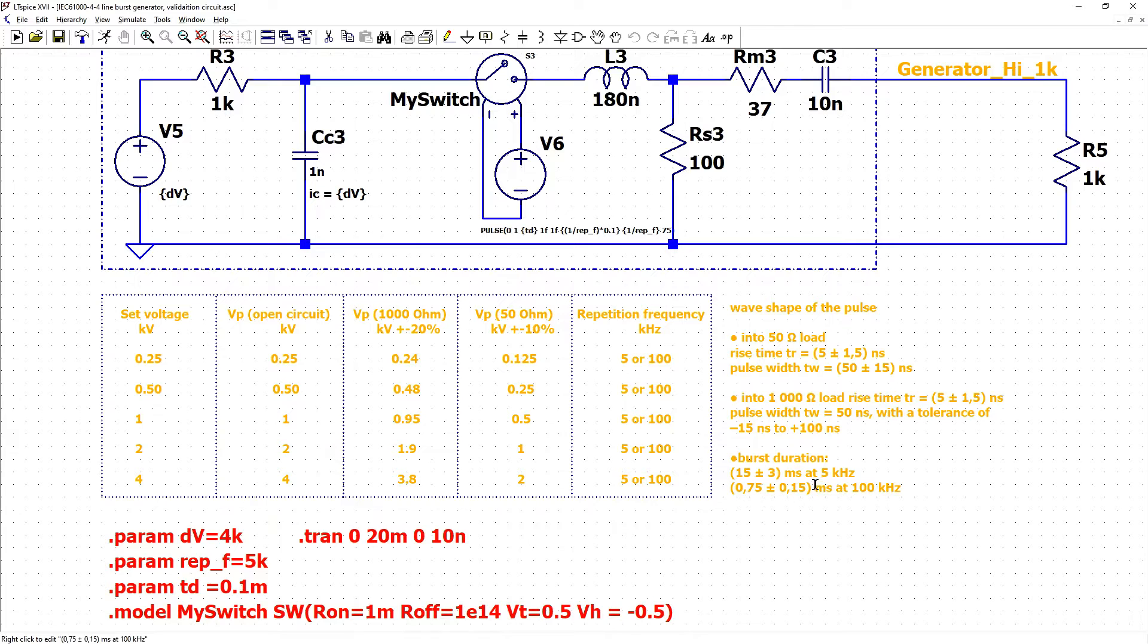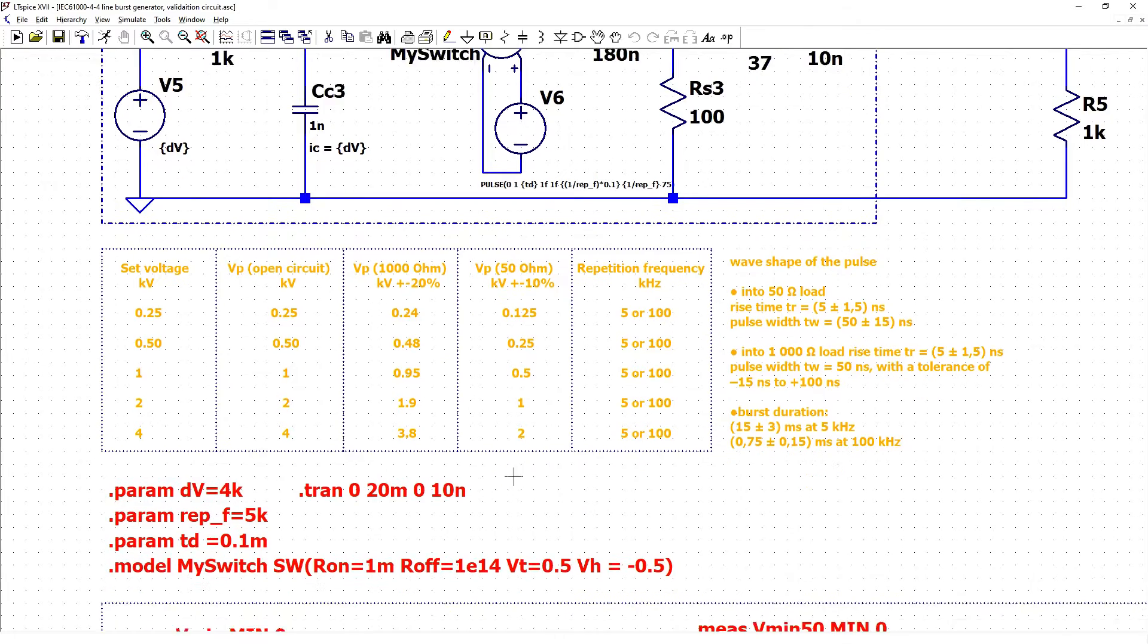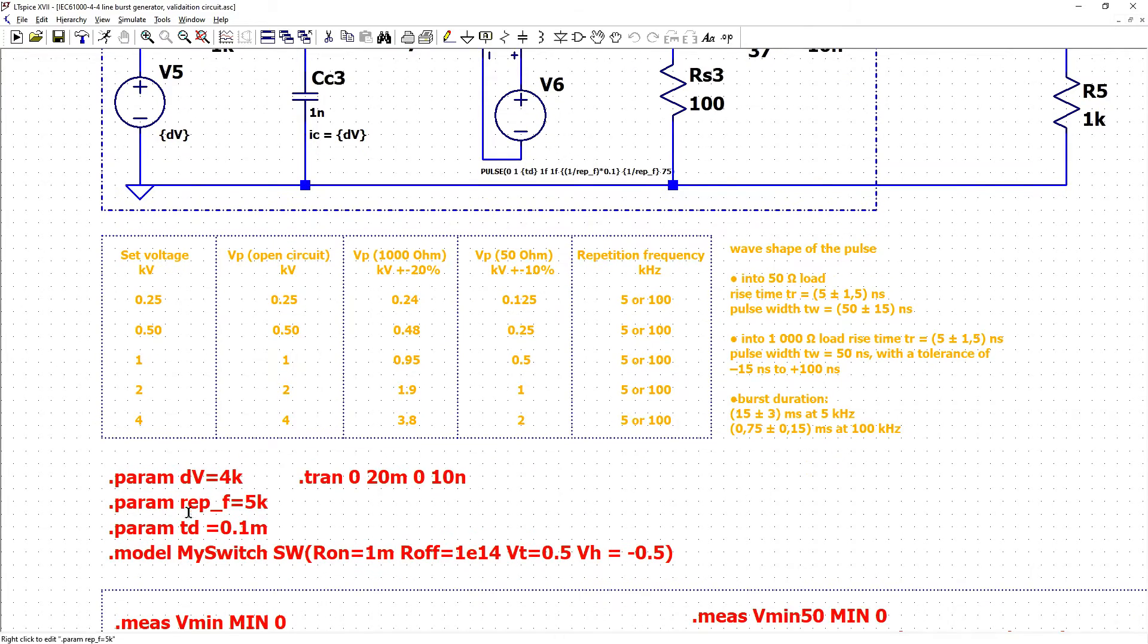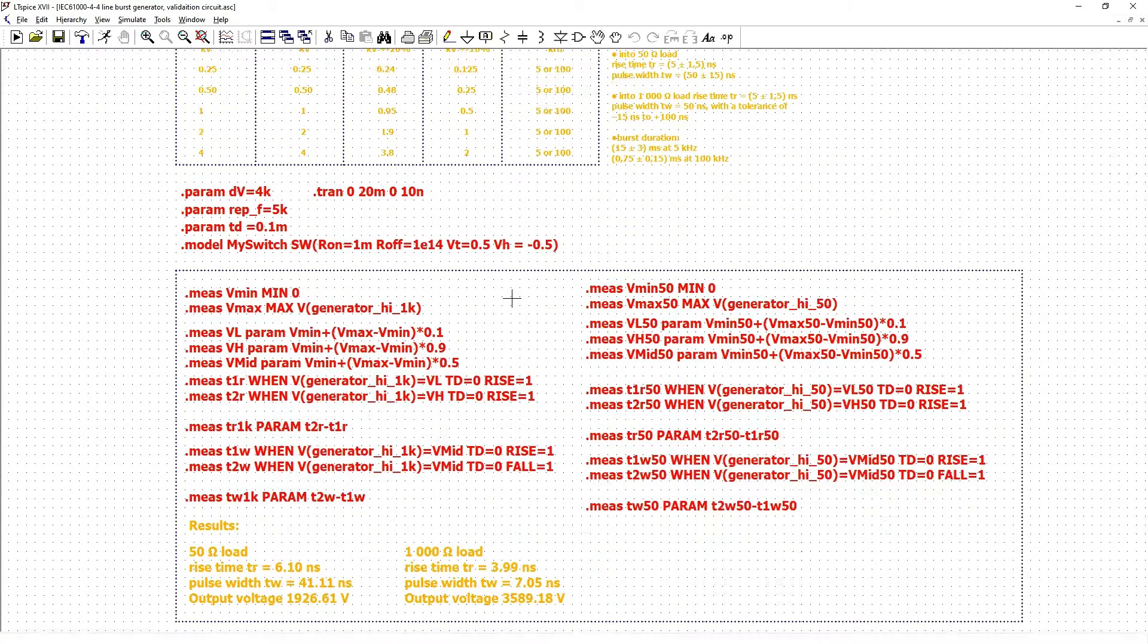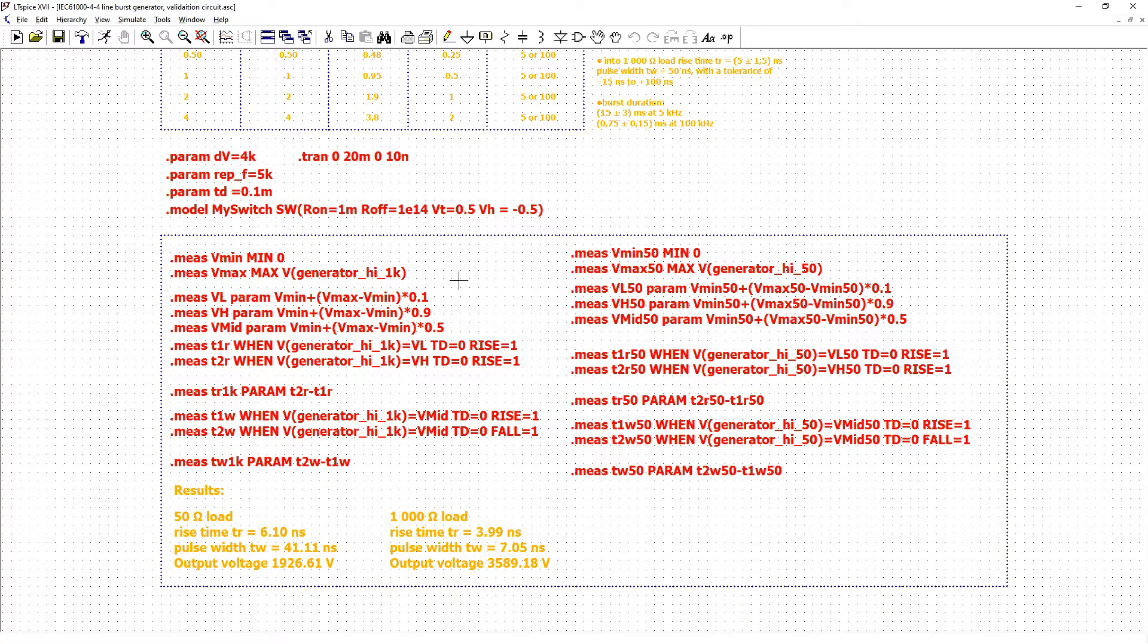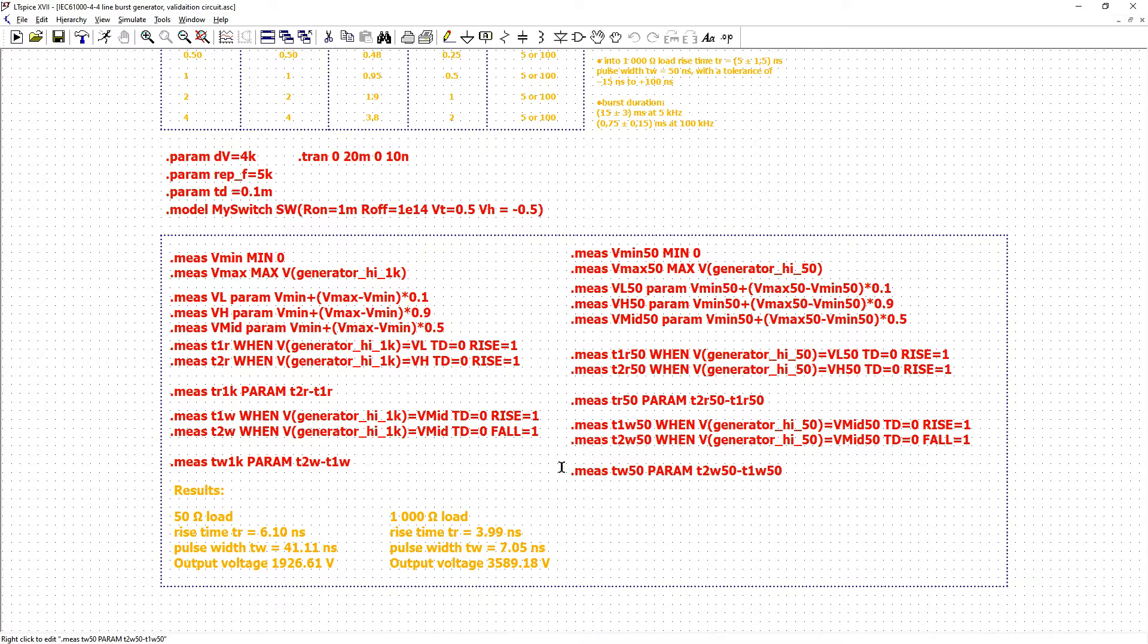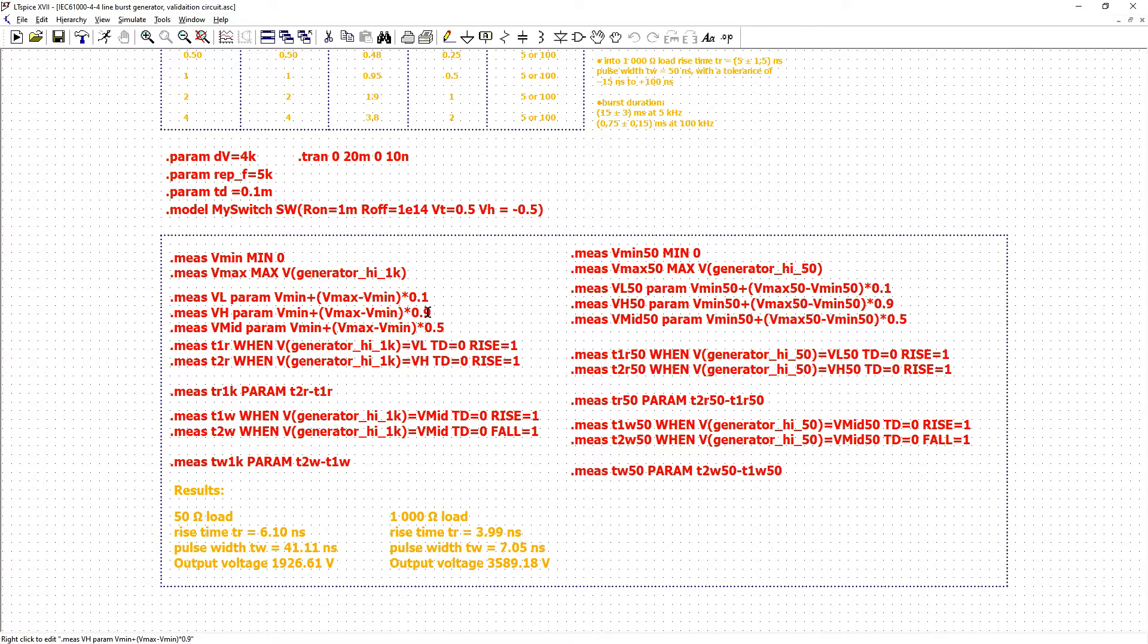The burst duration at 5kHz is 15 ms but at 100 kHz is 0.75 ms and we have our parameters here but also we have measurements when we measure values for 1k ohm load and 50 ohm load. With minimum value, maximum value.